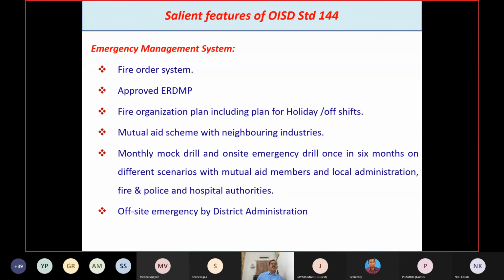As per OISD standard 144, for the emergency management system, the facility should have a fire order system, and the ERDMP, emergency response and disaster management plan, approved by PNGRB, should be made available. A fire organization chart, including a plan for holidays and off shifts, should be available both while working and during holidays, and it should be displayed distinctively in the facility. A mutual aid scheme with neighboring industry should be established. A monthly mock drill, and an on-site emergency drill once in 6 months on different scenarios with mutual aid members and local administration, fire, police and hospital authorities, should be carried out. An offsite emergency drill for the district administration should be carried out at least once in 2 years.